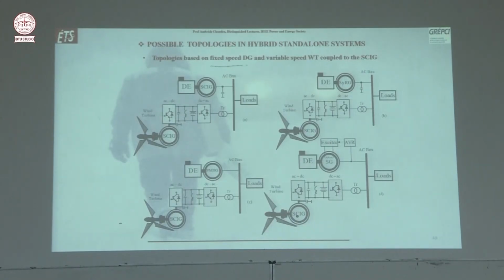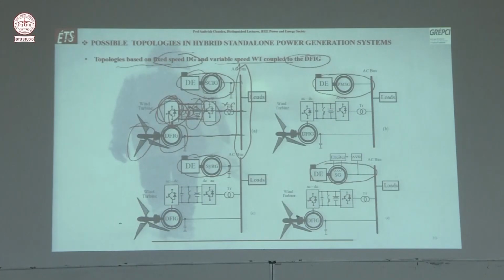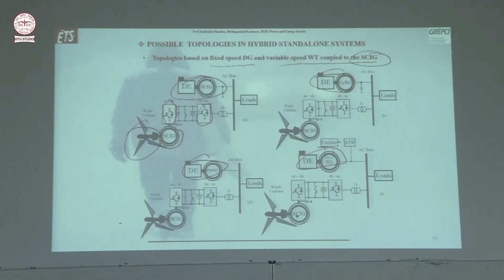Again, topologies based on fixed speed diesel generator and variable speed wind turbine coupled to squirrel cage induction generator. See, different types of machines you can use for the diesel generator, and with the wind turbine you can use a squirrel cage induction generator. Here you need a full size back-to-back converter, while in DFIG you have one third size of this. With squirrel cage, because on the rotor side there is no winding, on the stator only you can connect back-to-back full size converters, and this is the DC bus where you have battery bank and dump load, etc.